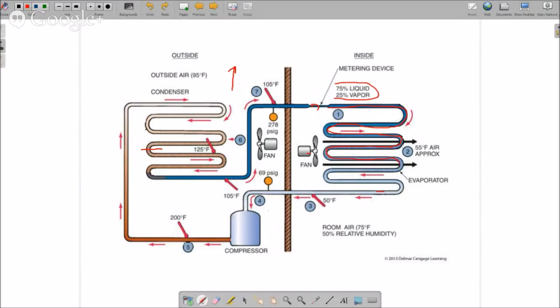But because there's too much refrigerant in the system, instead of being 100% vapor at the end of the evaporator, it's still changing state - there's still liquid in the system. It works its way through, still changing state, and we bring liquid back to the compressor. It might be only 10% liquid and 90% vapor, but we still have liquid nonetheless.